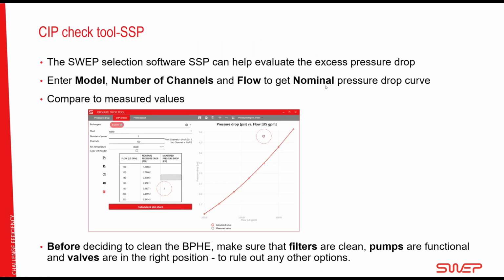We have some tools in SSP, our calculation software. It can help you by using the model that you're using, the number of channels, and please note channels, so it's not plates. So if I'm writing 100 channels, that means 200 plates, since it takes 2 plates for a channel. And then you can enter the flow, and in this pressure drop tool, you will be able to get what is the pressure drop that you're supposed to have over the heat exchanger with this data.